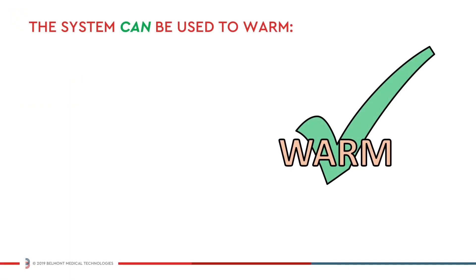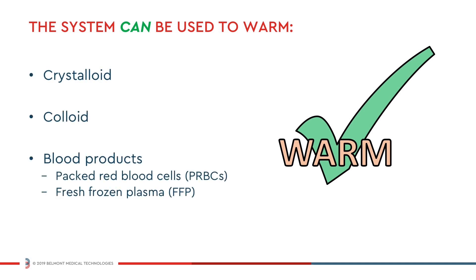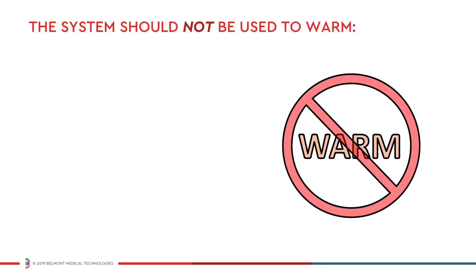The Buddy Lite can be used to warm crystalloids, colloid, and anticoagulated blood products, including packed red blood cells and fresh frozen plasma. The system should not be used to warm platelets, cryoprecipitate, or granulocyte suspensions.